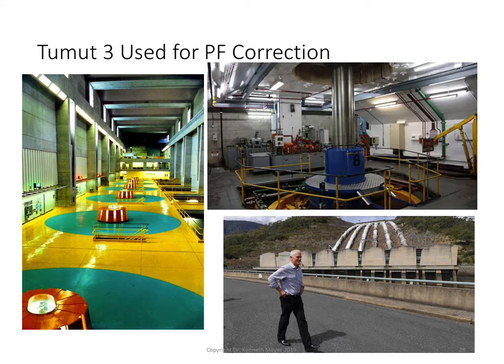So another place that you can find power factor correction that I should also mention as part of this lesson is synchronous motors. One of the places in New South Wales where synchronous motors are used to do power factor correction is at Tumut 3 Power Station. And you can see here the transformer floor at Tumut 3 Power Station. These three machines down here are not only generators, they're also motors with what they call underslung pumps. So those three machines at the far end of the hall can be generators and they can be pumps.